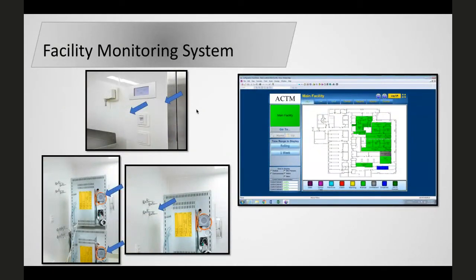We've got a facility monitoring system that's computerized, so it's monitoring all of our equipment and our rooms 24/7. So you can see the map of our facility on the right here. So if anything goes outside of the specifications that we've set, we get text messages on our cell phones, and the map will go yellow or red, depending on what the value is. And then you can click on the map and zoom in to see exactly what piece of equipment or what parameter is out of spec.